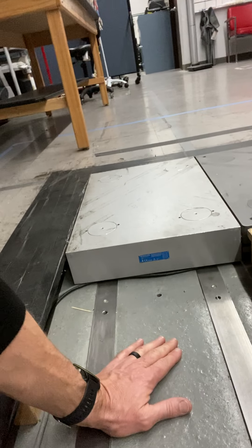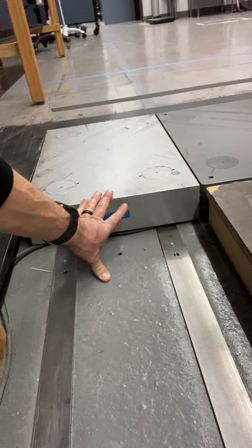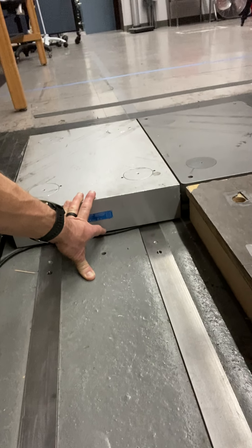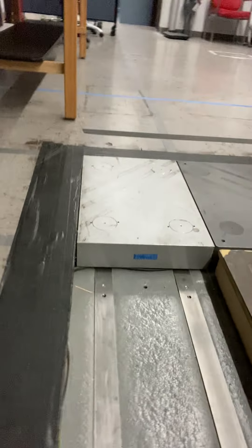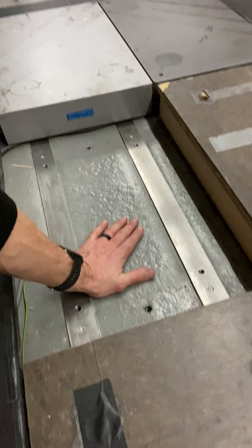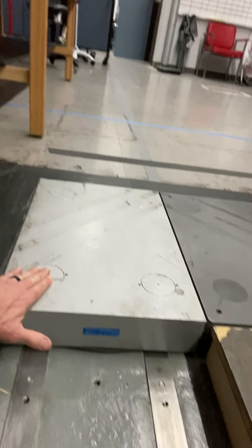It's so important that this platform is on a solid foundation. If the foundation moves, then this force platform is going to move and you're not truly measuring the ground reaction force — you're actually measuring the flex in the floor. So if you put a force platform on a second floor of a building you can run into problems because that floor will vibrate. Ideally your biomechanics lab has a force platform on the ground floor with a big chunk of cement and metal rails on a very stable, solid surface.